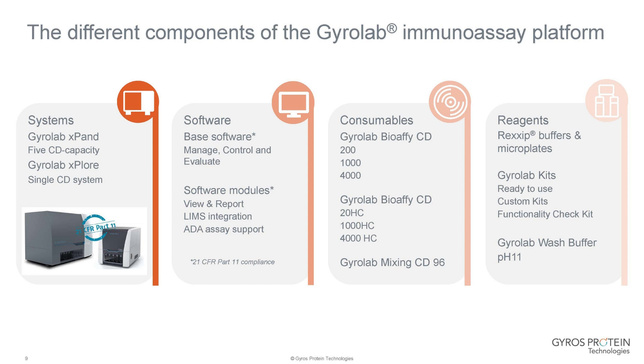The instruments are designed to operate in regulated environments as they are 21 CFR Part 11 compliant. We also have software that allows us to manage, control, and evaluate data, as well as plan and perform curve fitting. We have particular modules for LIMS integration into Watson, for example, but also modules supporting anti-drug antibody assays and affinity measurements. All our software is CFR Part 11 compliant.